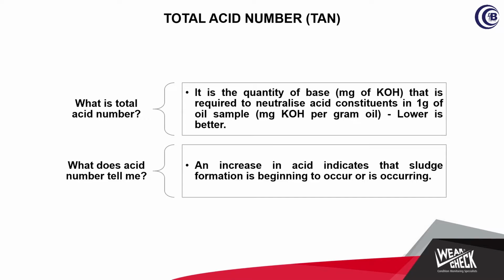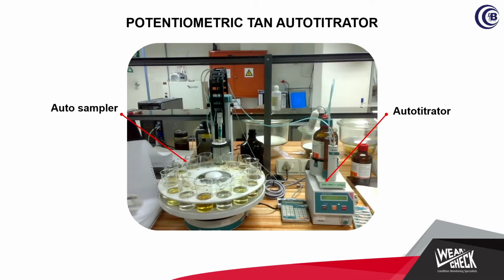It's impossible to get a light oil, yellow or white water type color, with a high acid. Acid will change the color of the oil. It is, however, possible to get a dark oil with a low value. That is an exception, but it's possible. But you can't get a light color oil with a high acid value. That is not possible. But acid does a lot of damage in your transformer.